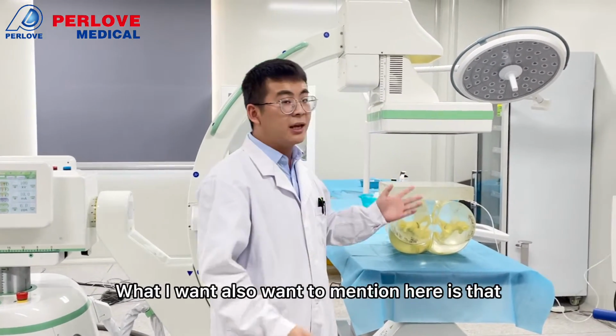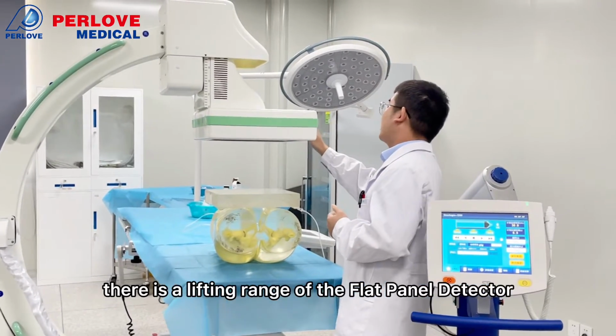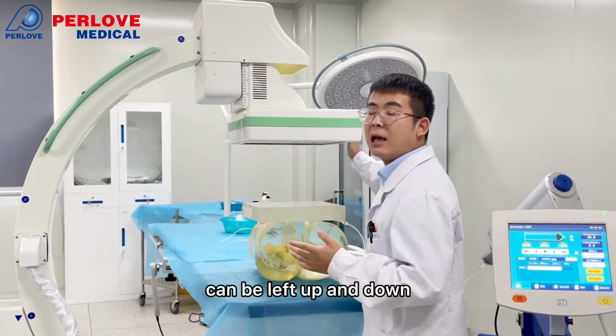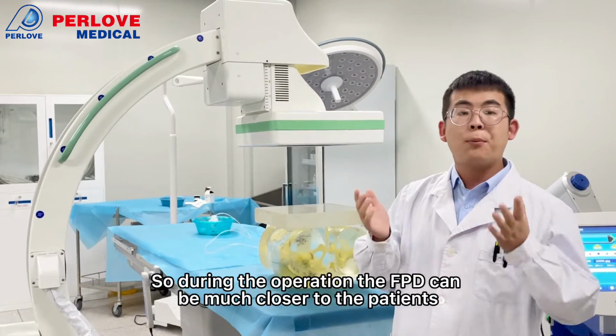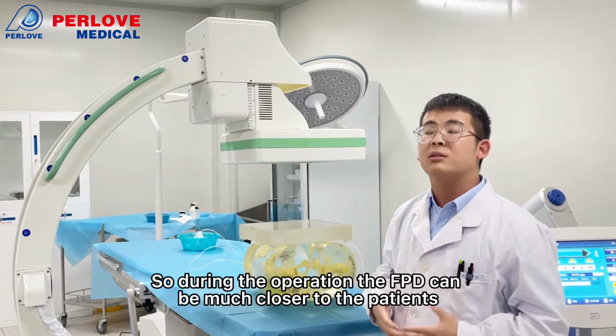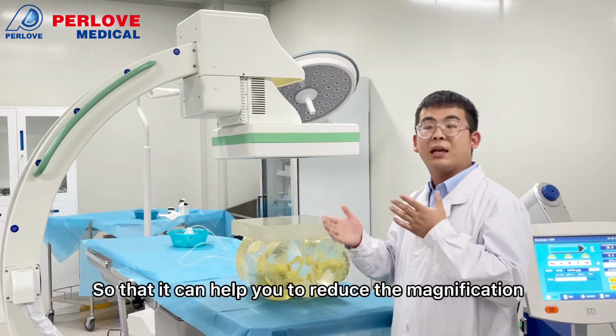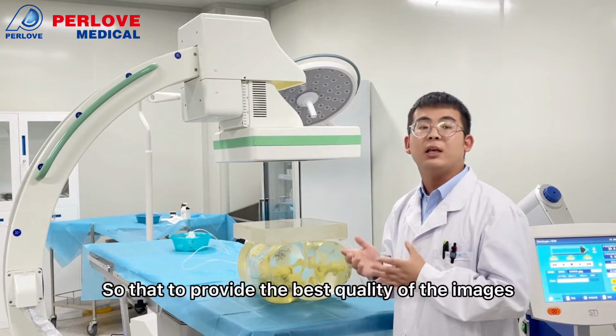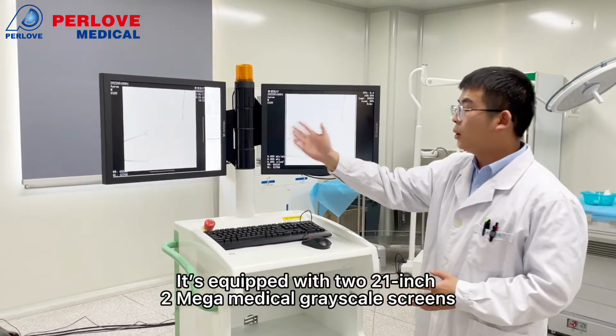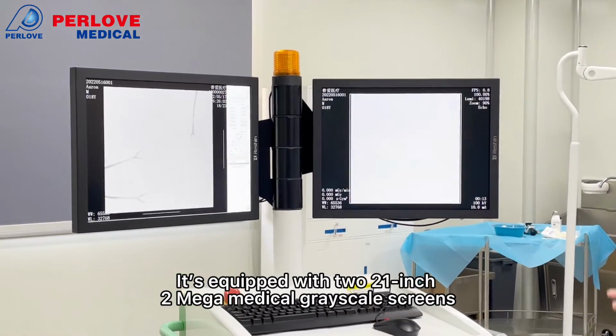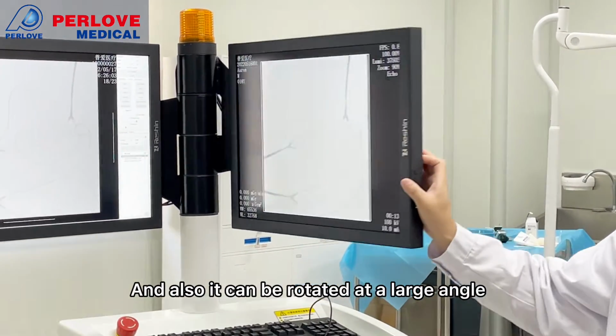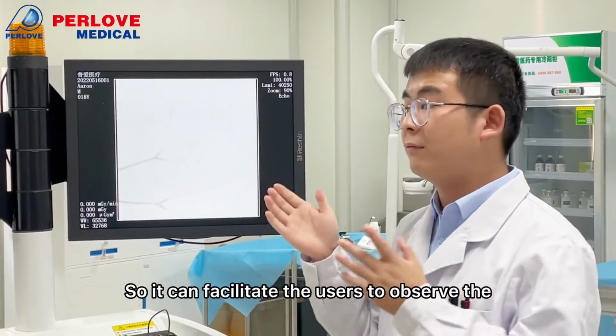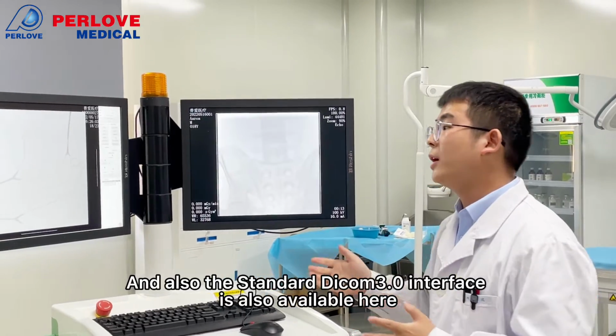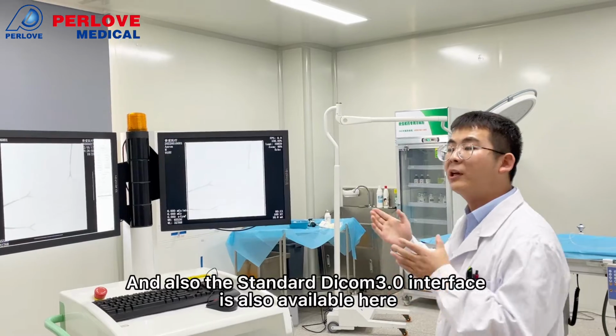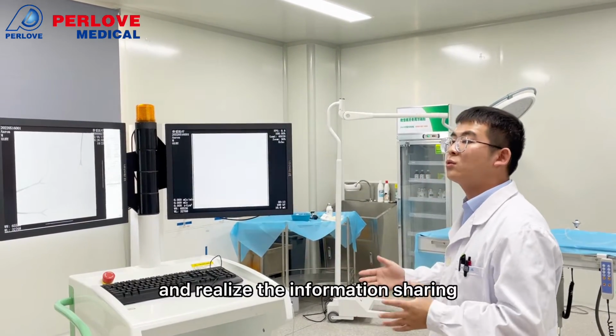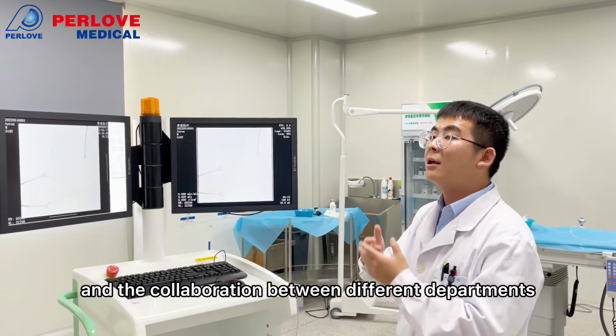What I also want to mention is the lifting range of the flat panel detector. It means the flat panel detector can be lifted up and down. So during the operation, the FPD can be much closer to the patient, which helps reduce the magnification and provide the best quality images. And here you can see our workstation. It's equipped with two 21-inch 2 mega medical grayscale screens, and it can be rotated at a large angle, so users can observe the images at different angles. The standard DICOM 3.0 interface is also available, which can easily connect to the hospital PACS system and realize information sharing and collaboration between different departments.